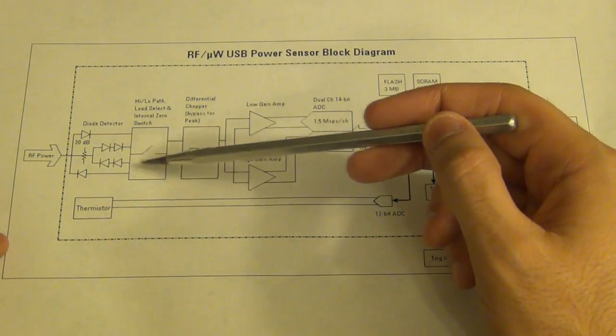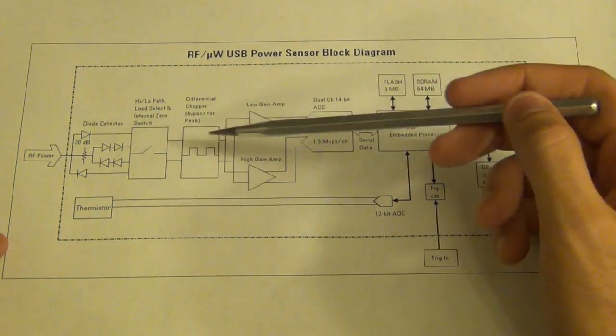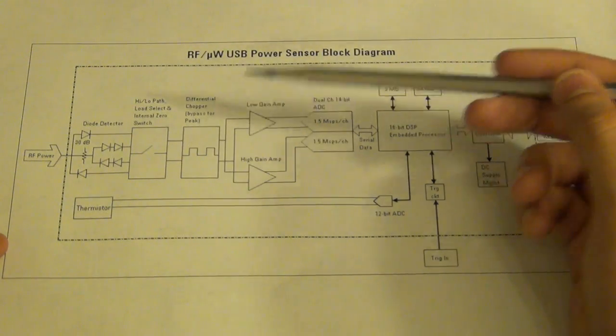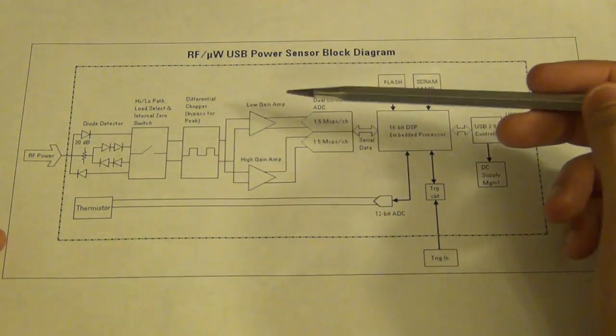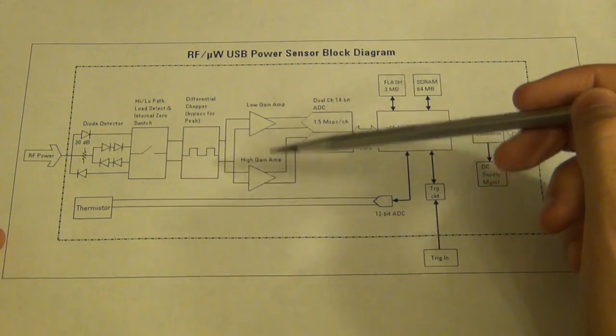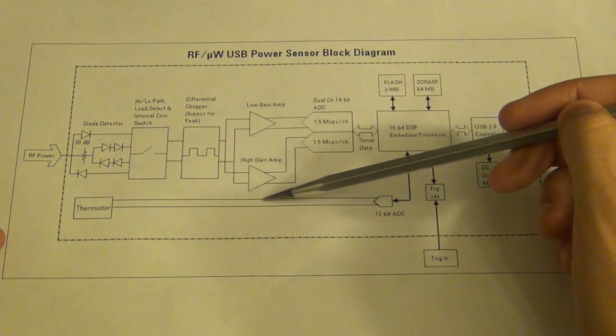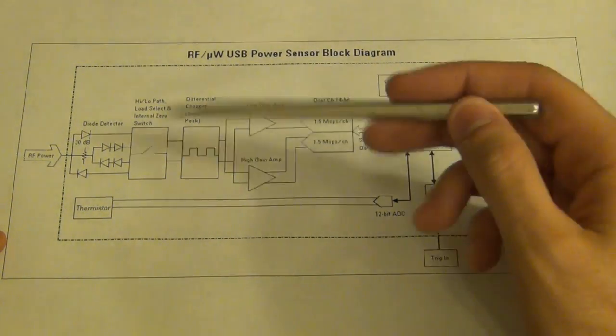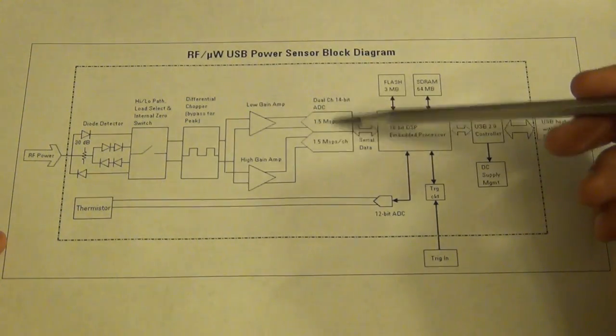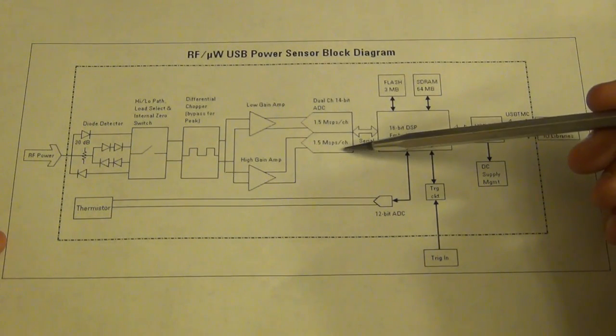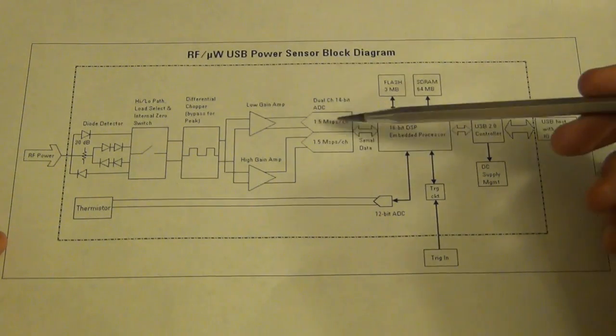There's a switch that selects the high path and low path, and a differential chopper used to drive a low gain amplifier and a high gain amplifier. This combination of chopper, low gain, and high gain amplifier ensures proper placement of that voltage within the optimum dynamic range of the 14-bit ADCs that follow.